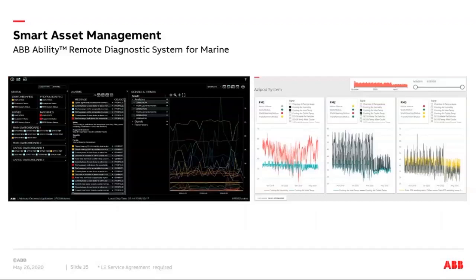Let me give you a few examples. On the slide now, we see on the left side the onboard user interface. Typically, this is the user interface that is located in the ECR and is meant for the engineers and electricians working in the engine control room to make sure that they have access to the correct information should a critical incident or any type of incident occur. It consists of three main sections. On the left-hand side, there is a KPI section. The RDS system also runs quite sophisticated edge calculations, and KPIs output from those calculations are displayed to indicate, for example, the status of a closed cooling circuit of a frequency converter or the condition of a rotating machine, based on the vibration data that we are collecting. These KPIs are made available for the onboard crew.